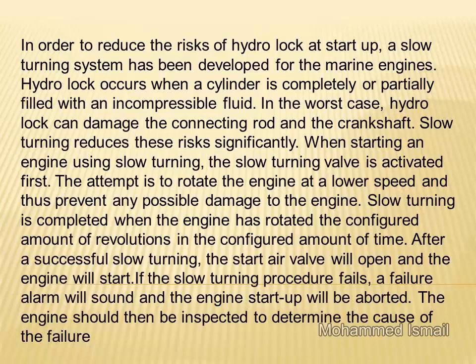When starting an engine using slow turning, the slow turning valve is activated first. The attempt is to rotate the engine at a lower speed and thus prevent any possible damage to the engine. Slow turning is completed when the engine has rotated the configured amount of revolutions in the configured amount of time.